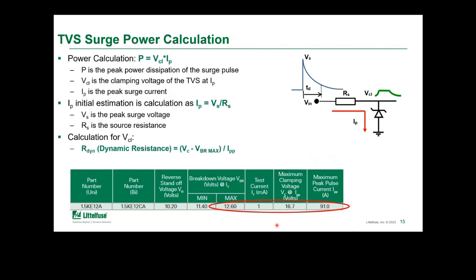And this can be calculated using values from the data sheet. So it's basically the peak clamping voltage minus the breakdown voltage, divided by the peak current, that provides us with the dynamic resistance. If we take that dynamic resistance multiplied by the peak current that we determined earlier, and then add that to the breakdown voltage, we can come up with a peak clamping voltage. And then by multiplying that peak current and that peak voltage, we come up with the estimated power dissipation that's required, so we know what size of TVS that we need.